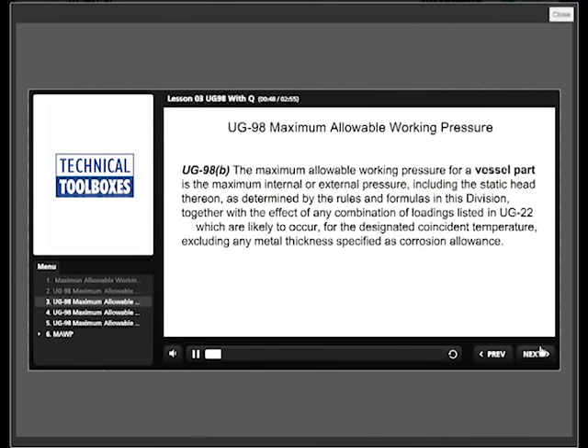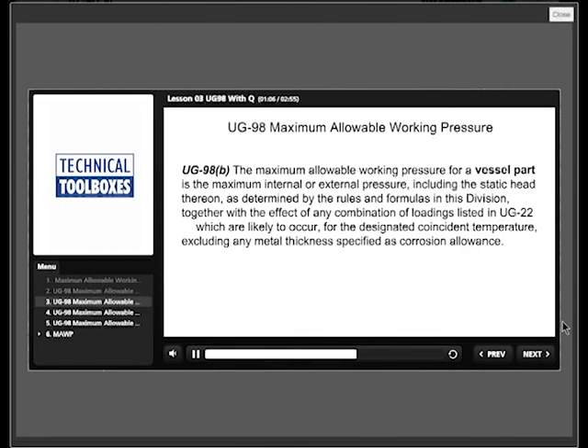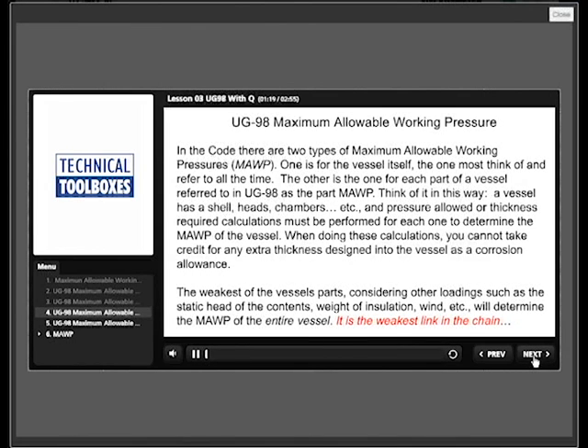UG-98B: the maximum allowable working pressure for a vessel part is the maximum internal or external pressure, including the static head thereon, as determined by the rules and formulas in this division, together with the effect of any combination of loadings listed in UG-22, which is likely to occur.